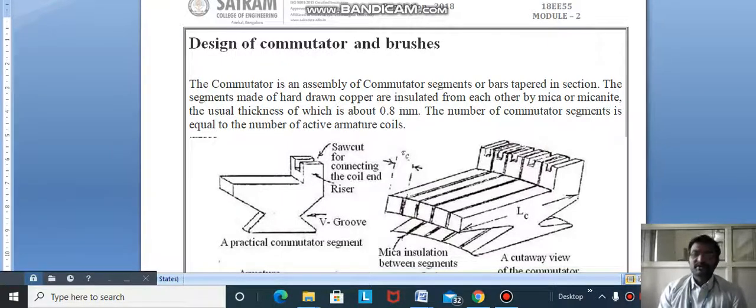Hi to all, in this video we're going to see about design of commutator and brushes of a DC machine. The commutator is an assembly of commutator segments or bars tapered in section. The segments are made of hard drawn copper and insulated from each other by mica or micanite. The usual thickness is about 0.8 mm.